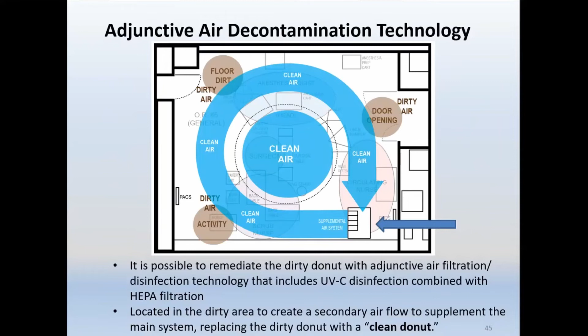Adjunctive air decontamination technology is described in the CDC guideline for environmental infection control in healthcare facilities. And they quote, "As a supplemental air cleaning measure, UV germicidal irradiation is effective in reducing the transmission of airborne bacterial and viral infections in hospitals." And there are many hospitals right now, because of COVID, using these kinds of UV robots, either in isolation rooms or maybe a COVID unit. So that's been used a lot. But the uniqueness of adding HEPA filter with UVC is really key.